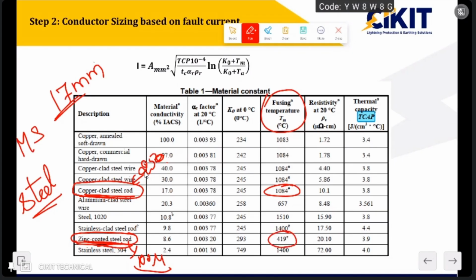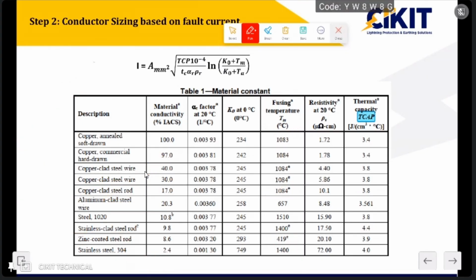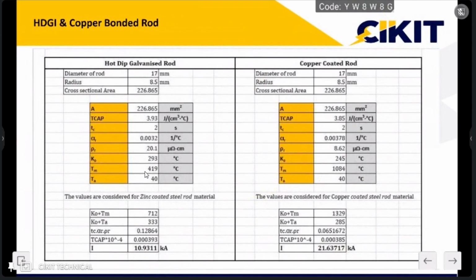So for example, if I'm providing huge current, then the copper rod can withstand this, but the zinc over the MS will get peeled off. So because of this fusing temperature, even though the core materials are of the same dimension, the current carrying capacity of the copper coated rod will always be higher than that of the zinc rod. So this is the calculation for comparison.